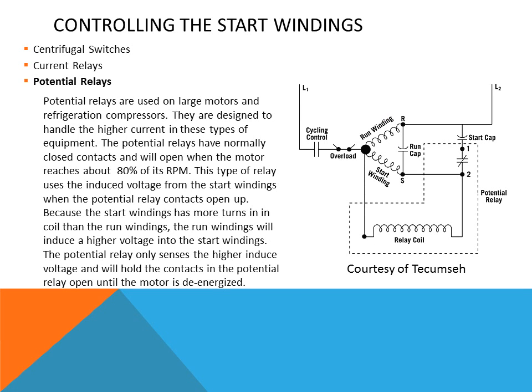Potential relays are used for larger motors and compressors and are designed to handle higher current. They are sometimes called voltage relays because they use the inductive voltage from the start windings — which generates a higher voltage than the applied voltage — to send voltage to the relay coil. This relay coil only senses the higher inductive voltage. The potential relay has a normally closed set of contacts that will open once the inductance in the start winding increases, and will remain open until the compressor is de-energized.